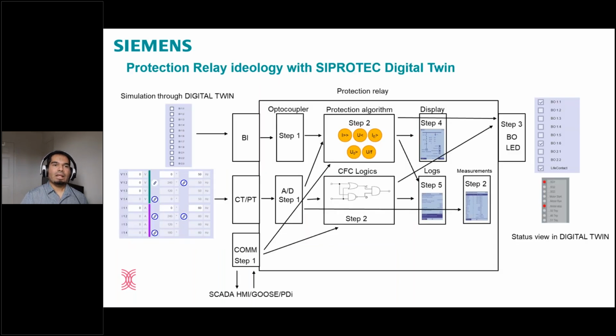And now, if you recollect in the previous slides, I showed you how the traditional protection relay ideology works. So how would the same ideology look on the digital twin? On the left-hand side of the relay, traditionally you would use analog inputs or digital inputs, which are fed from a test kit, like an Omicron or a Megger or Doble. So this now can be replaced with simulated values using the digital twin application. As you can see, we have binary inputs simulation, and then voltage and current simulation.